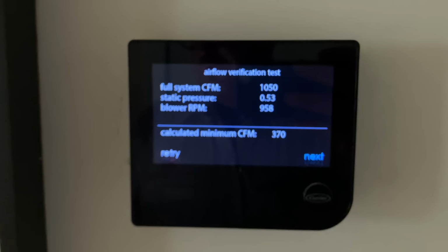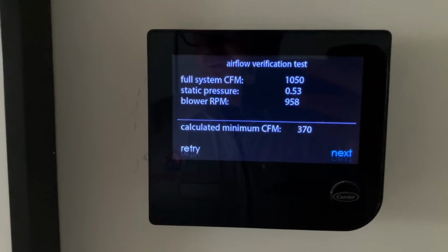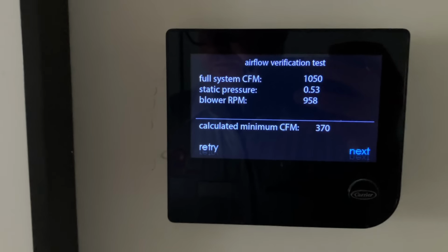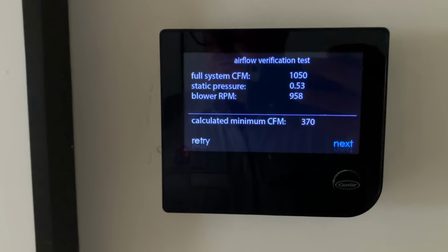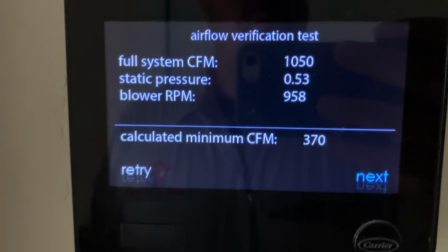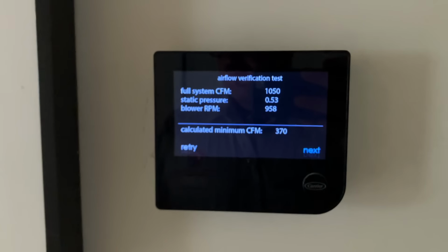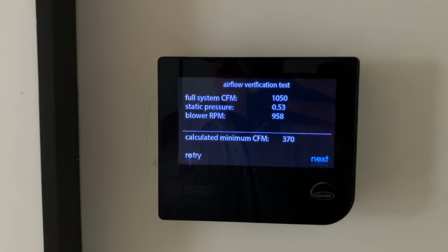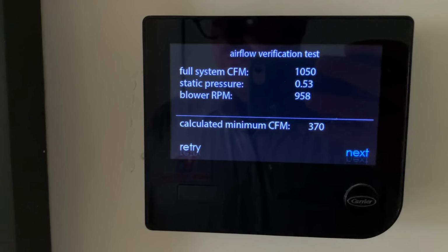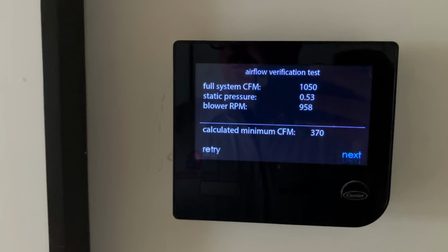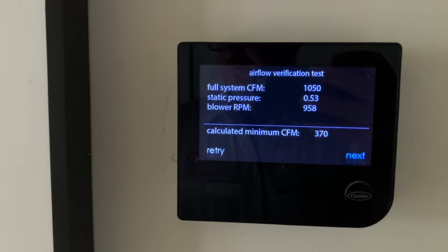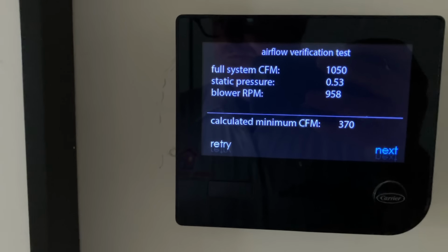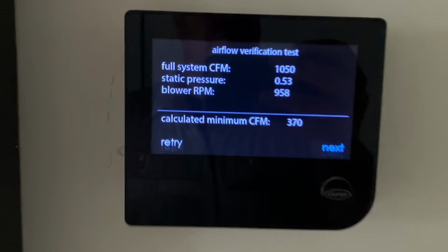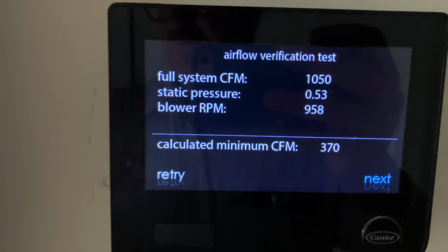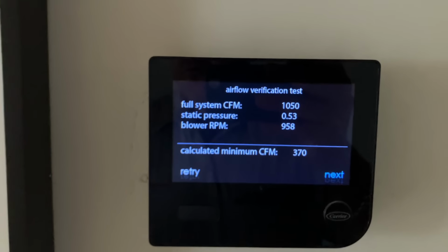0.53 isn't terrible, isn't horrible, but this is exactly why I love having this kind of information. A communicating system can tell us what the blower is doing, how much resistance it's seeing in the ductwork. And look at the bottom, calculated minimum airflow, only 370 CFM. That's the beauty of inverter technology. This thing doesn't have to run like an old school 3-ton system at full blast every time there's a call. It can ramp up or down and match the load.